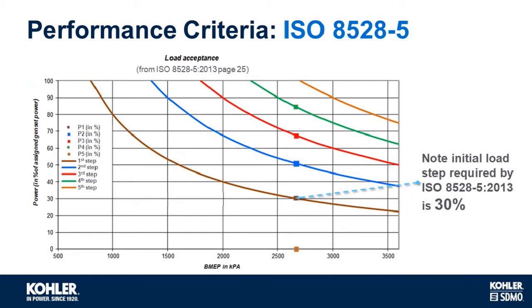The brown line shows that the initial load step capability should be 30%. The second load step, which is the blue line, should be an additional 20%, so a 50% step in total, and so on until 100% load is achieved.